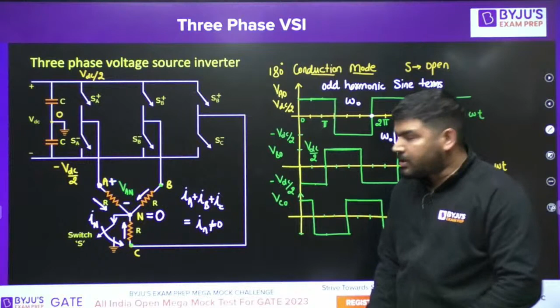Because if you look at the fundamental current, IA, IB and IC, if you add the fundamental component of the current, it will become 0, because they are 120 degrees apart. Similarly, if you add the 5th harmonic, 7th harmonic, the total sum will be 0. But for triplen harmonics like 3rd, 9th, 15th, if you add them, they will not be 0, because they are in the same phase. That's why they will be added and flow through the neutral point, through this ground point, through this switch. So this wire will contain the triplen harmonic current. Is it fine? I hope you understood.